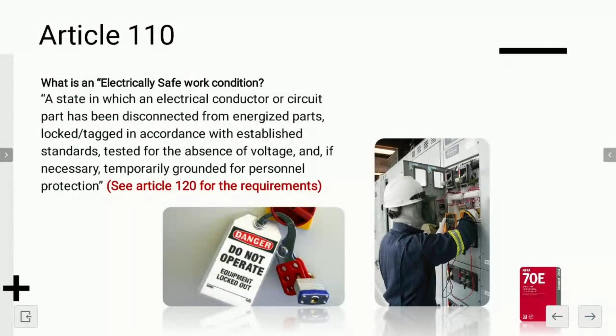Okay. What's an electrically safe work condition? Well, the 70E says that's a state in which the electrical conductor or circuit parts has been disconnected from its energized parts, and it's locked and tagged in accordance with your facility's or your employer's established standards. And then we test it for the absence of voltage. And sometimes, if we need to, we have to use temporary grounds as well. Part of that standard we just read said if you're going to be in what's called the limited approach boundary of exposed energized conductors or circuit parts at 50 volts or higher, then we have to turn it off and lock it out.